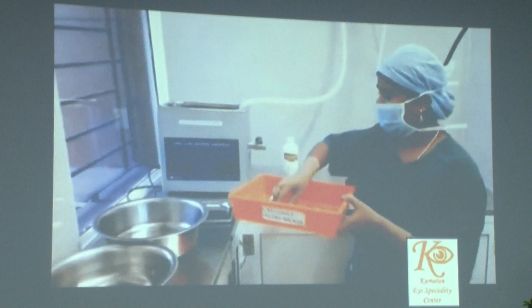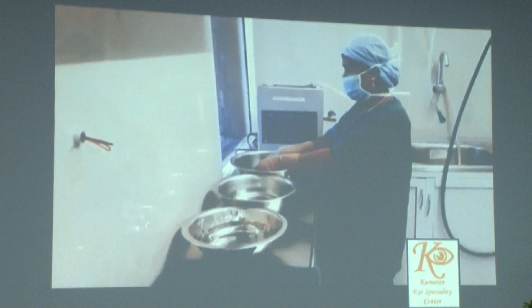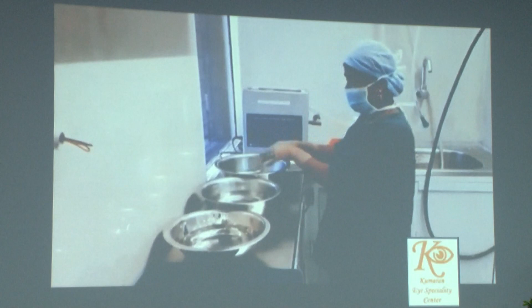These instruments are then processed in an ultrasonic cleaner. InstruClean can be added, and preferably warm water is used. Once this is processed, all the instruments are then again rinsed using the 3-bin technique. They are sequentially rubbed with a fine bristle brush to ensure that all the blood and body fluids are removed. Teach your staff to not hurt themselves and the instruments, because sharp instruments can get blunt.